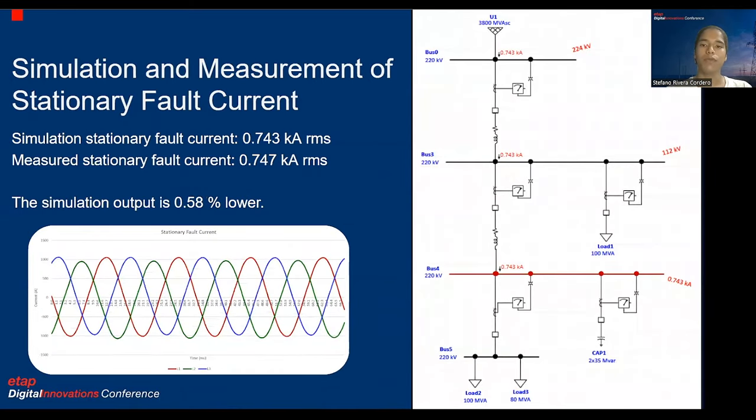Finally, the value obtained from the simulation for the stationary fault current was 0.743 kiloamps, and the measured value was 0.747 kiloamps. In this case, the deviation from the simulation is even lower, being only 0.58%.